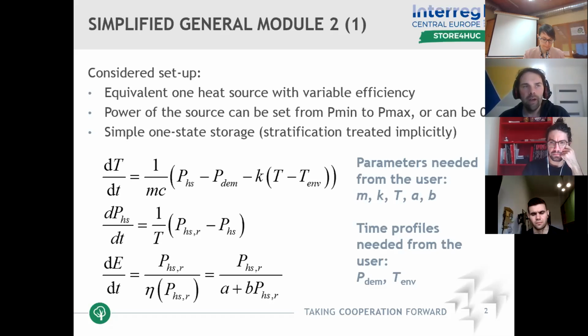So this would be the time granularity with which we could provide the advice in the most detailed way. But we figured out that advice in 15-minute intervals would be too complicated to follow and to schedule and program for the local automation. That's why we can make it less frequent in time, such that, for instance, for 3 hours we keep the same power of the heat source.